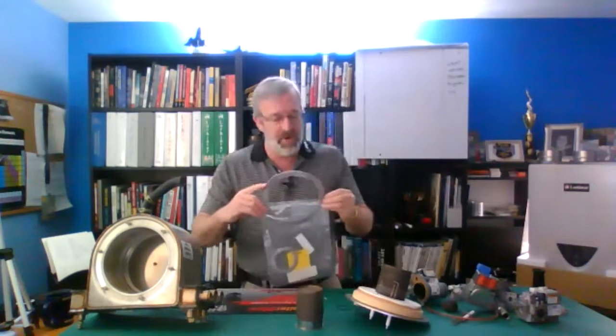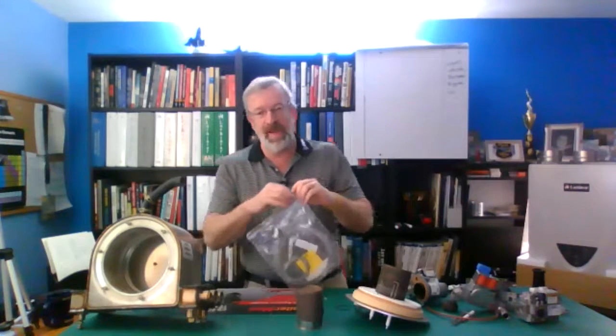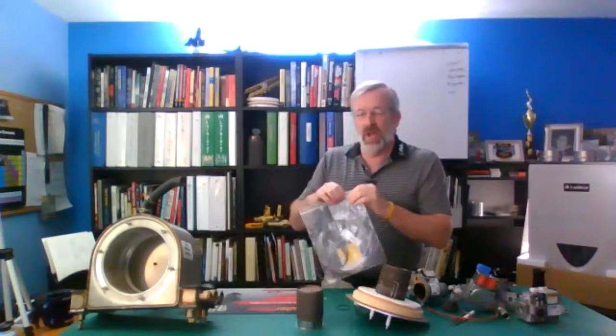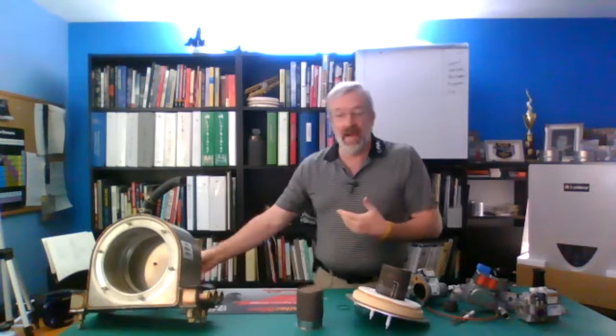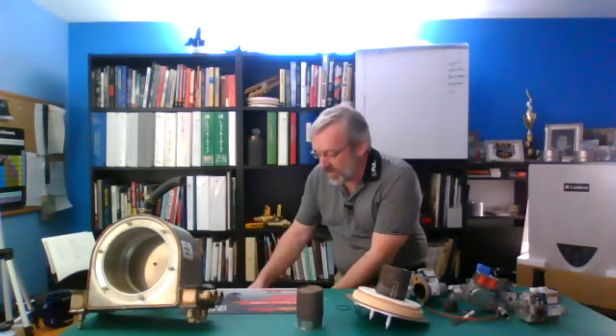and I know that Ray just put on there that the rope gaskets come in the tune-up kits. They don't anymore. They're no longer selling those separately. That's from the heat exchanger manufacturer themselves. So you have to buy a whole door if you need a new rope gasket. I still have the original rope gasket that I got with my tune-up kit 12 years ago. Haven't had to use it anywhere yet. Don't see a lot of those getting used. So that's the gasketing on those. Nick, hopefully that answers how to get that burner out of there when you're going to do that on your question there.